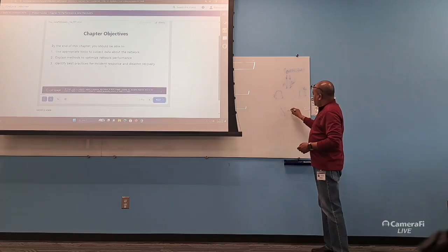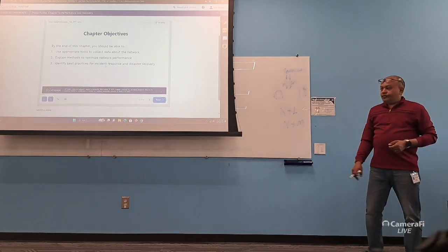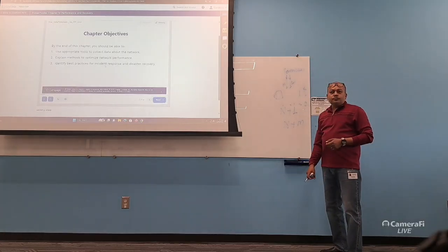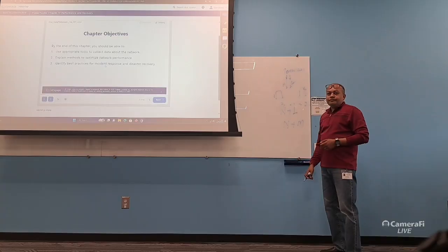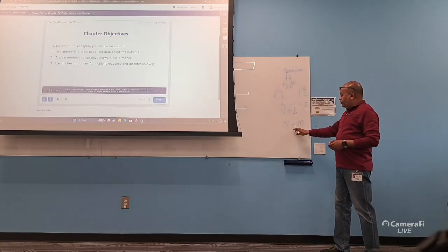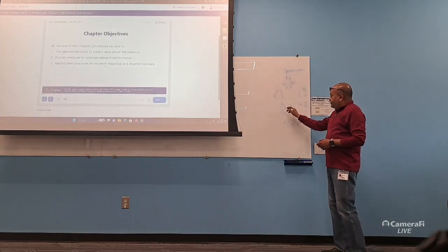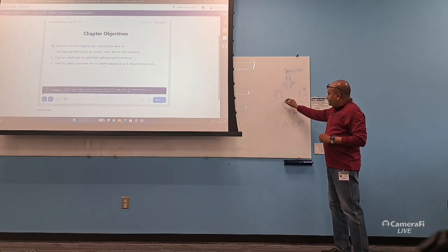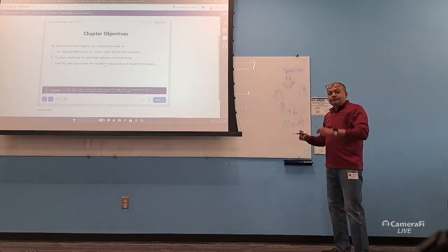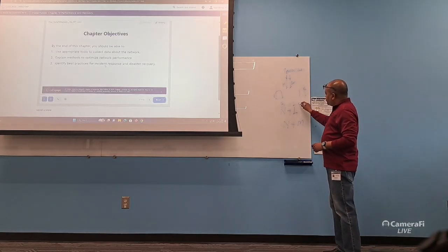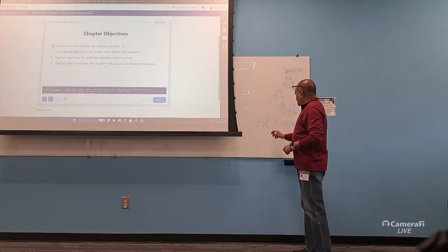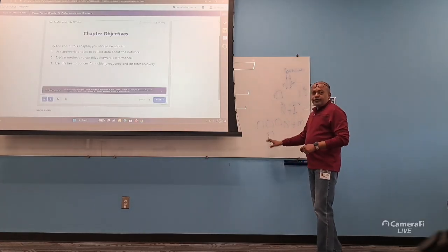So it is the concept of N plus 1 or N plus M. N plus 1 means if I need 1, then I must have 2. If I need 3, then I must have 4. What is N plus M? If I need 3, I'm keeping only 1 for the redundancy, so that if 1 fails, let's say I have 3 generators, and I'm keeping 1 more extra for redundancy.